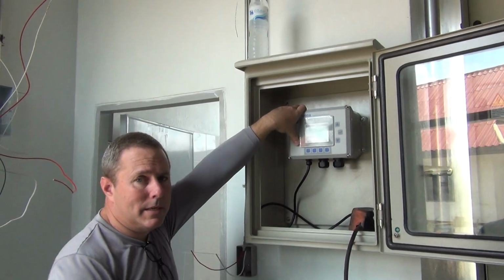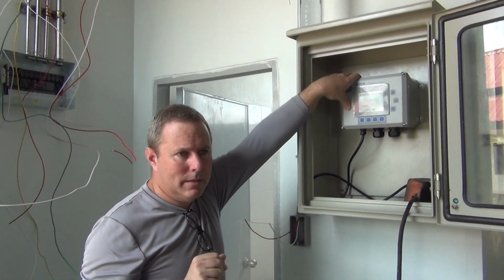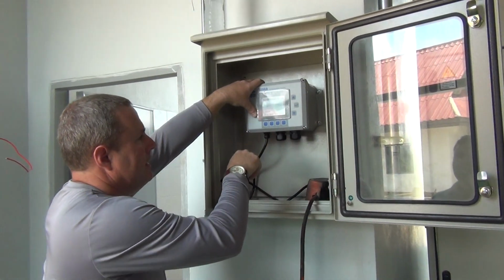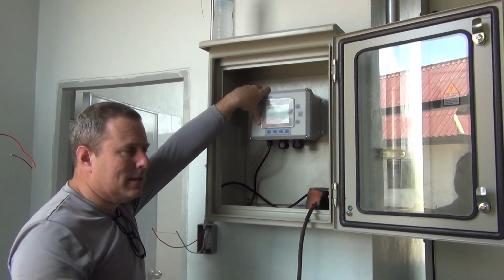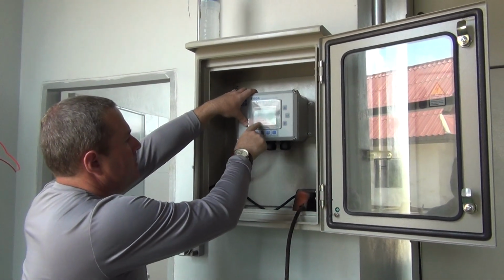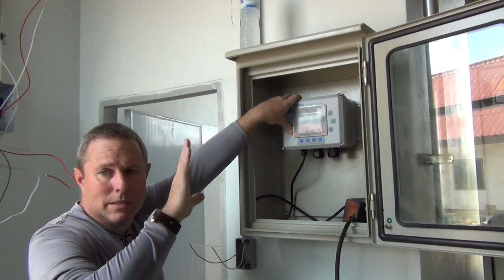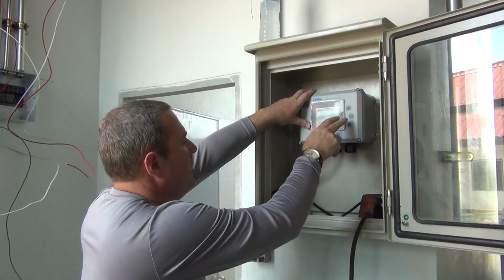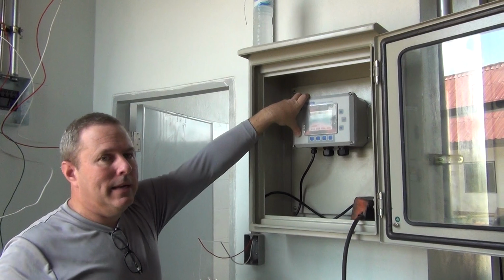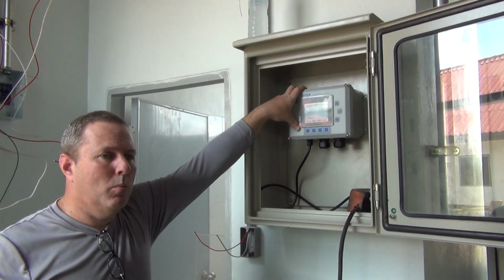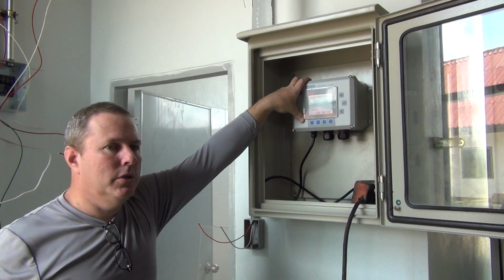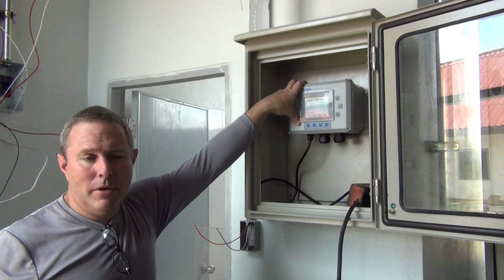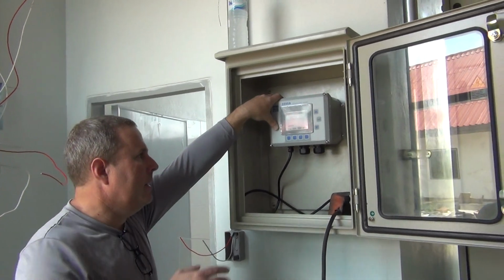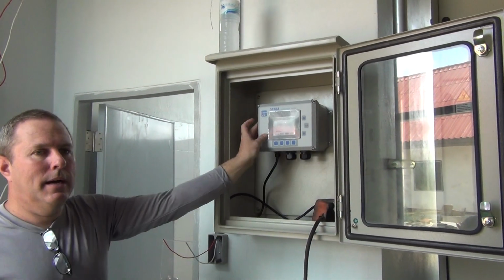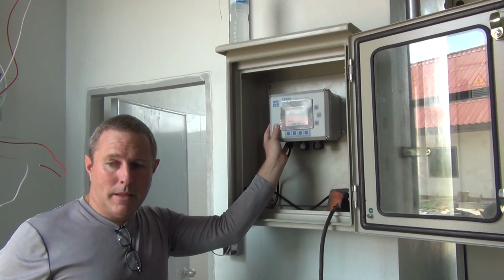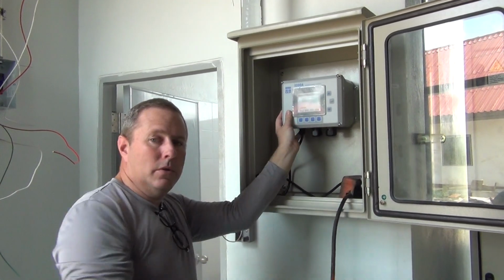The data logging, we've already set up for 1 per hour, correct? So then we go to date and time. We've already set that for the current date and time. So then we have display settings, which we've set up so that now you can see all the parameters. And now we get to downloader. Downloader is used when there is a firmware update. And to do that, you would take a laptop computer or a connected PC, you would interface it through a USB to serial, typically interface, and plug in to this unit.